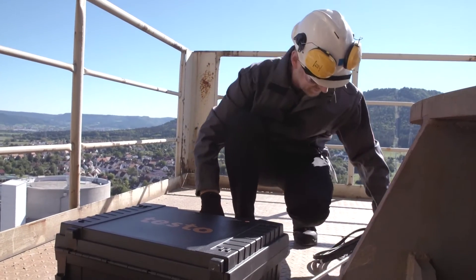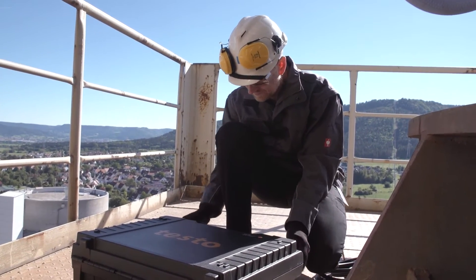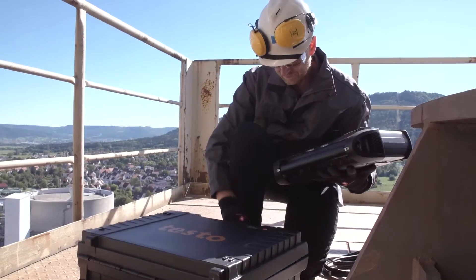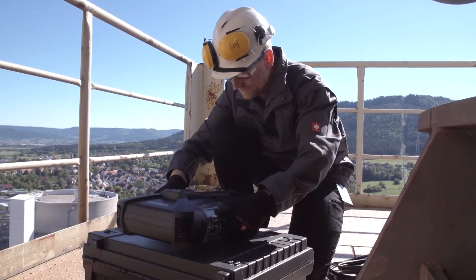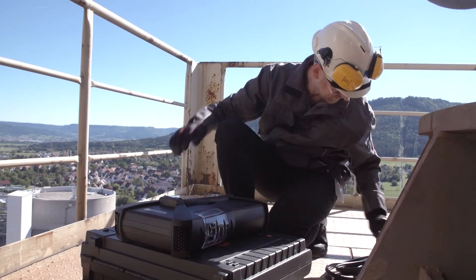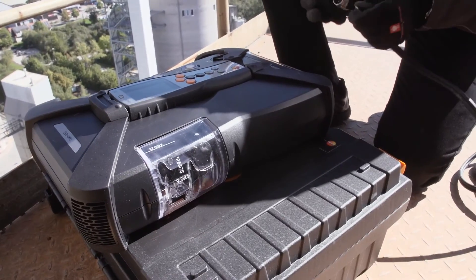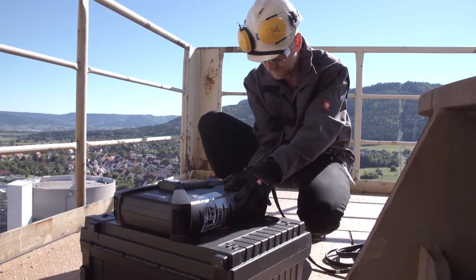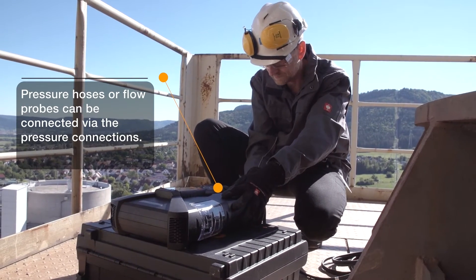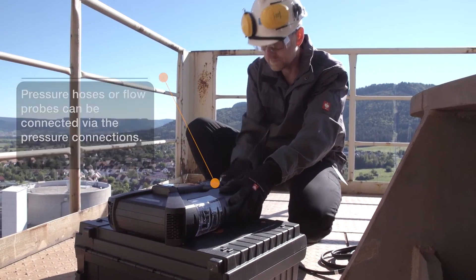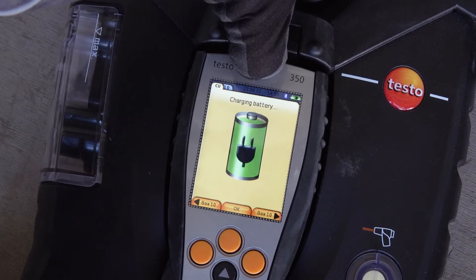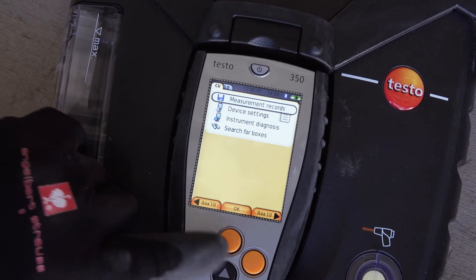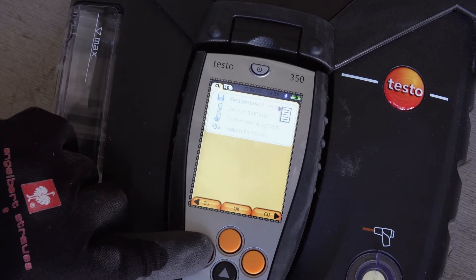The practical Testo 350 can be used effortlessly at any measuring location in the plant. For exhaust gas analysis, the Testo 350 consists of the analysis box with the removable control unit. To prepare for the measurement, plug the exhaust gas probe onto the connection socket of the Testo 350 and lock it in place. A combustion temperature sensor can be connected via the separate socket. After switching on via the control unit, the start screen of the Testo 350 is activated, and the control unit searches for connected analyzer units, showing them as independent tabs in the display.